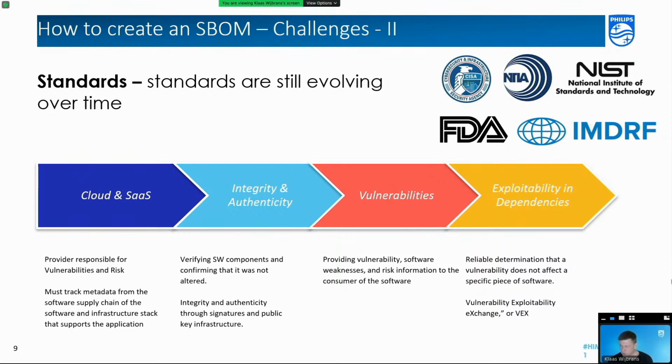But if you look at Europe, cybersecurity is also already part of EU MDR requirements. Europe has a different way of mandating these kinds of things than the US does. But in the end, we hope that we can converge on a number of common standards that will give us what they call the presumption of compliance with both of them, so that we don't have to do different activities dependent on who we deliver to.